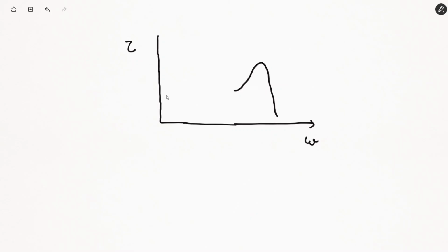This will start from actually here. So at one frequency, you can say F1, our torque speed profile will look something like this. At another frequency, our torque speed profile may get shifted and it will start from here. Fine. So at different frequency levels, our torque speed profile will look something like this, where F1 is greater than F2 is greater than F3.